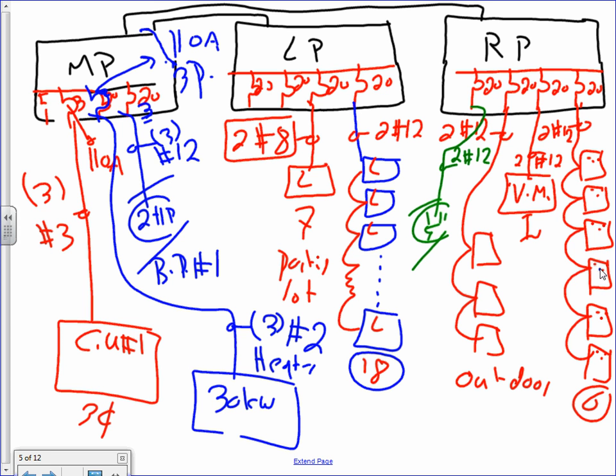Can anybody tell me why in the parking lot I pulled 2 number 8, even though I have a 20 amp circuit going to the parking lot? Voltage drop. Thank you, voltage drop. When you go to the parking lot, you don't pull anything smaller than at least number 8. Sometimes we pull number 4 even. So number 8, number 10, number 8 is common. So when you go to the parking lot, your conductors are going to be number 8. Why? Voltage drop. Okay? That's why I put the voltage drop.